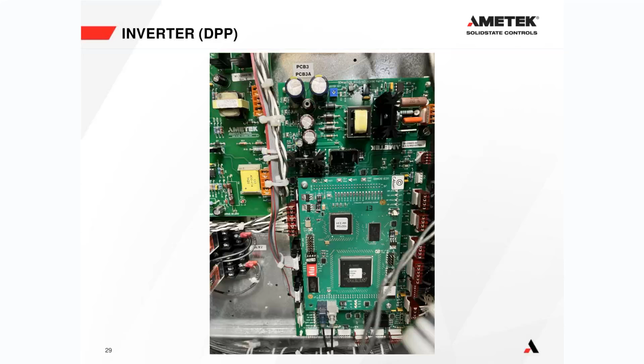This is the inverter control board, PCB3 and PCB3A. This one here is PCB3, and the one mounted to it is PCB3A. We call that our UCB, or universal communication board. That's where the firing signals that go to the IGBTs are generated - that's what turns the inverter on and tells it what to do.